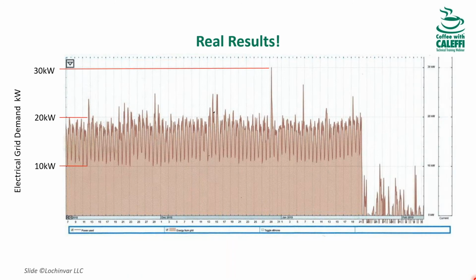When we installed the cogen system and put 25 kW into the system, utilizing 163,000 BTUs of heat, we brought their power consumption down to below their regular usage of 10 kW. This went a long way in developing the ROI on this facility, because it's a 24/7 operation.